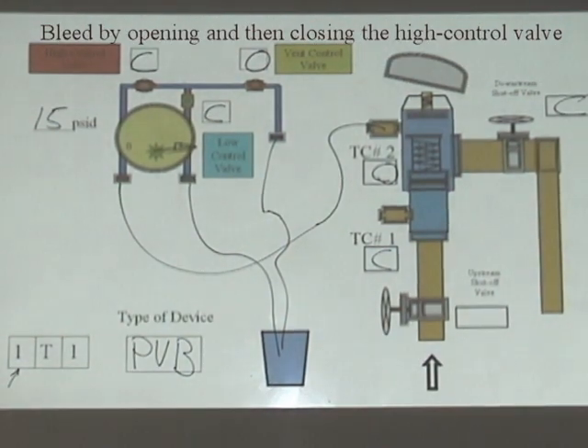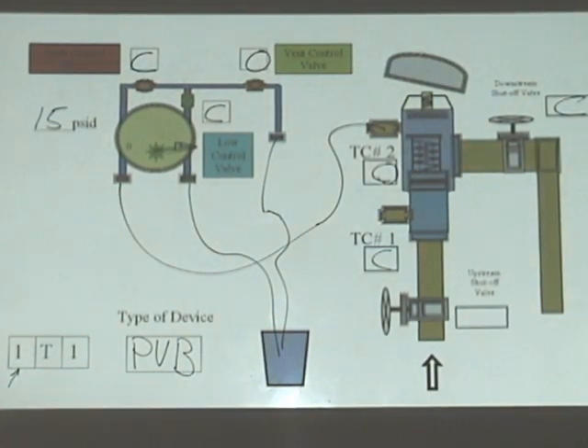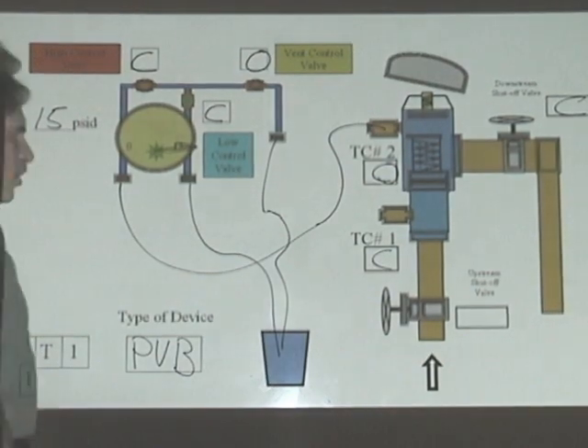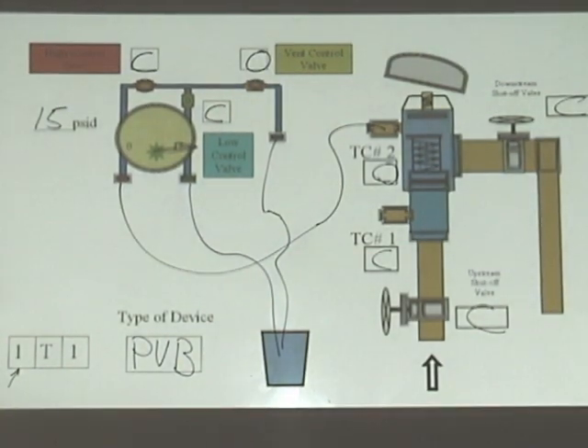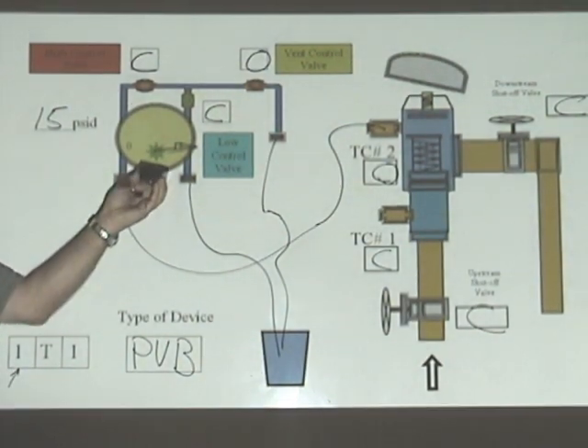Now, here comes the test. To test for no flow on a pressure vacuum breaker, we close down the upstream shutoff valve. We observe our test kit. If it's holding steady, that's telling us we tested under no flow.